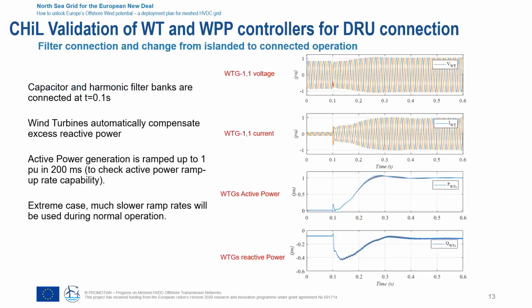The complete verification of all the wind turbine controllers includes a very large number of test cases. We are including here only some examples, so you can see the functionality of the complete system. So one of the first examples we see here is the operation when we connect the diode rectifier AC filter banks, and then when we ramp up to full power production.